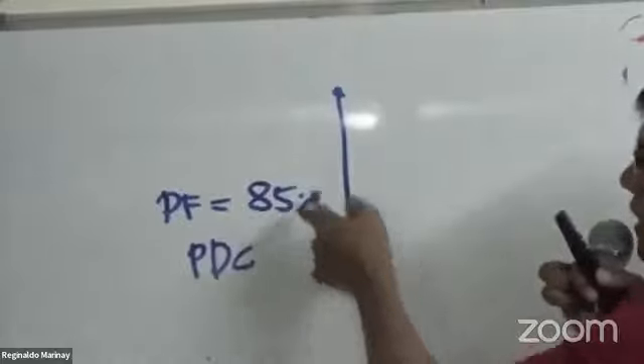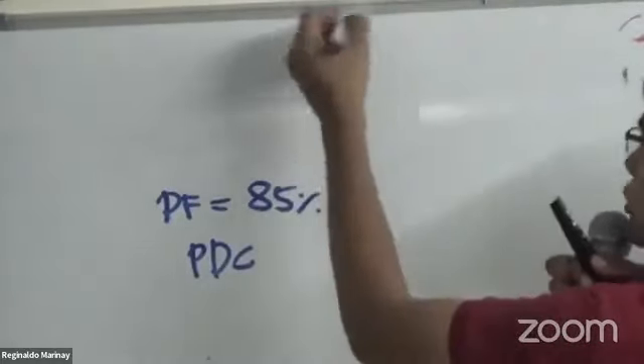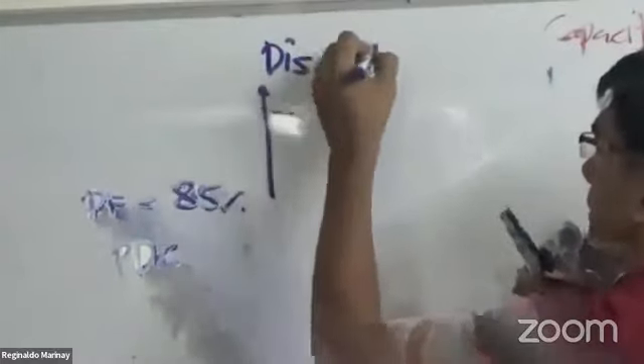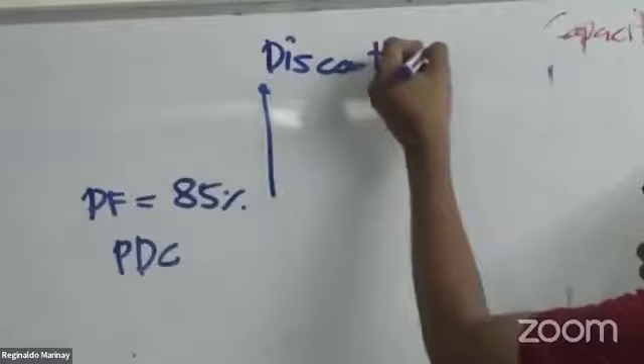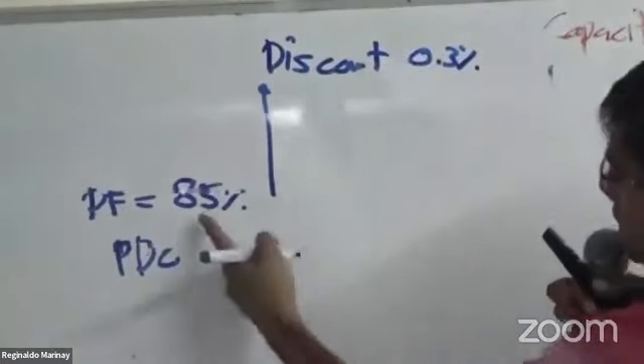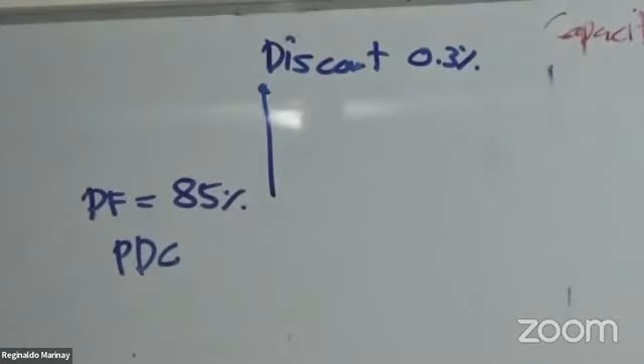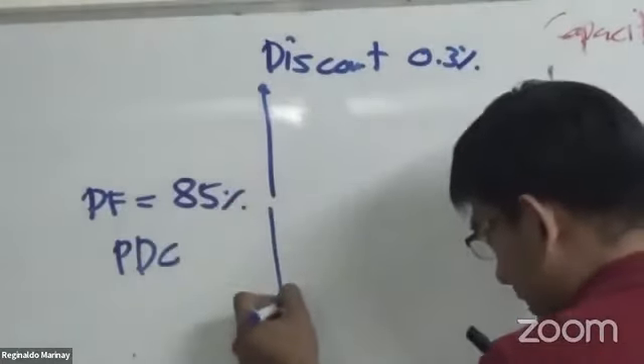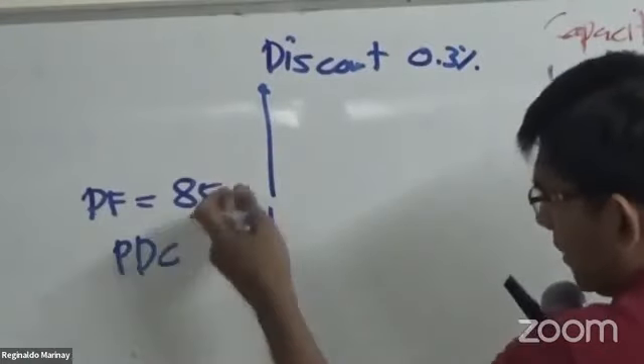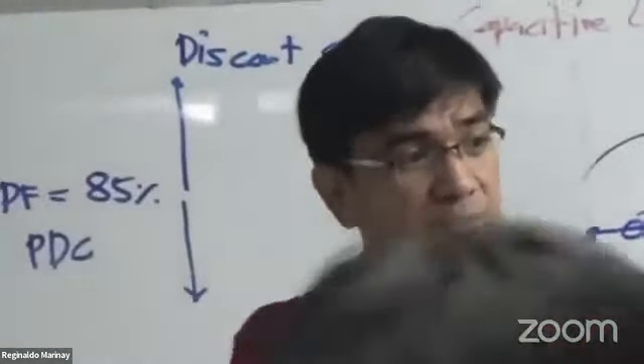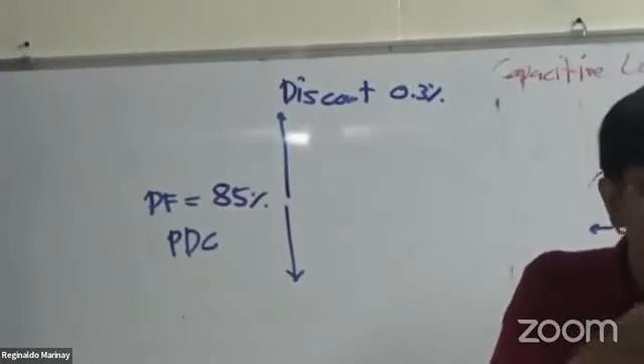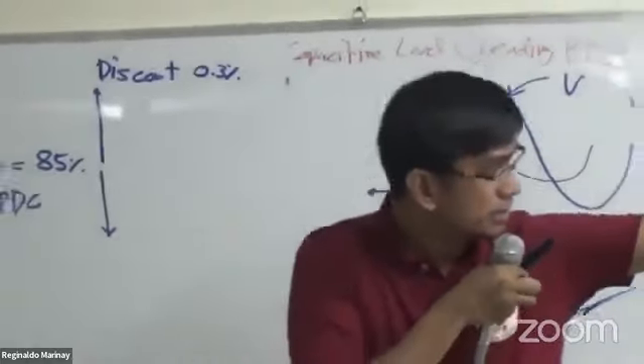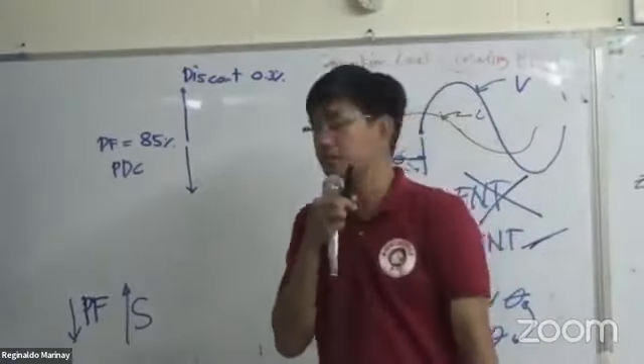If your power factor is higher than 85%, you will have a discount from Meralco, a discount of 0.3% for every percentage point higher than 85%. Later I'll show you the detailed computation. If you go lower than 85%, why would you have a low power factor? Because you have so many inductive loads. If you have so many motors, especially in industry, and you keep adding more and more motors, the power factor keeps dropping. If it was at unity, it drops as you keep adding inductive loads, which is why I drew that diagram earlier.